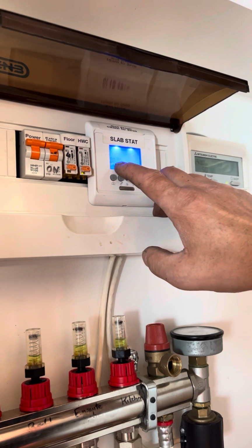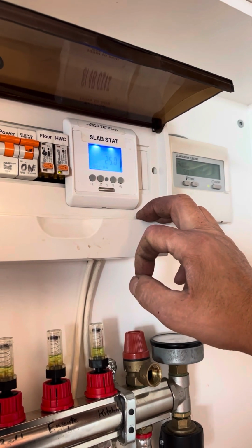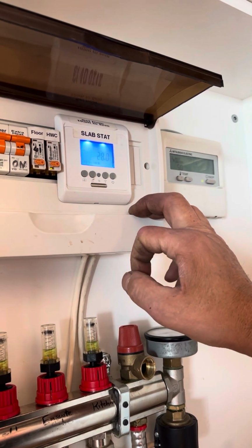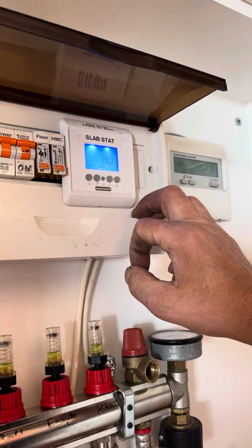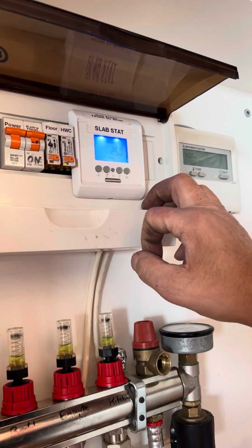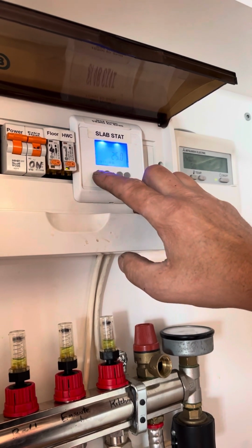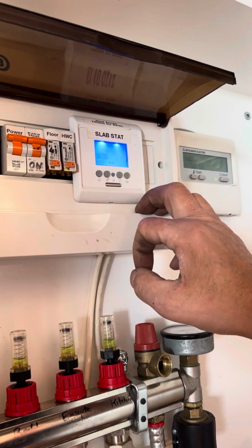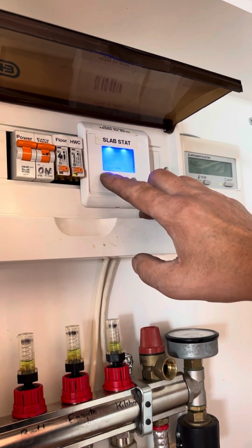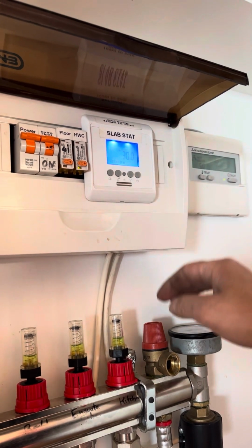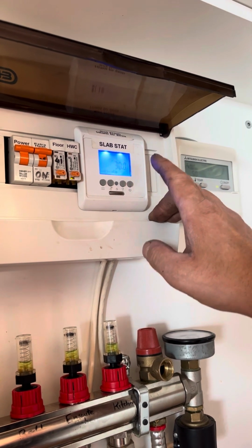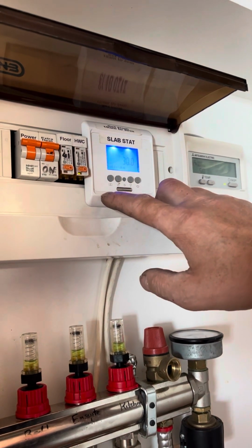So we can see at midnight we are asking for 25 degrees. Push it again. At 4 o'clock in the morning, we step it up now to 28 degrees, concrete temperature. At 8 o'clock in the morning, it drops back down to our base temperature of 25 degrees. And then at 10 o'clock in the morning, when you are generating solar electricity, hopefully you've got free electricity and you are running the heating system. It's now running at a maximum of 30 degrees. So if the floor gets up to 30 during the middle part of the day, it will turn off.